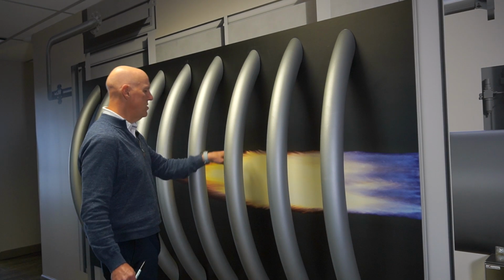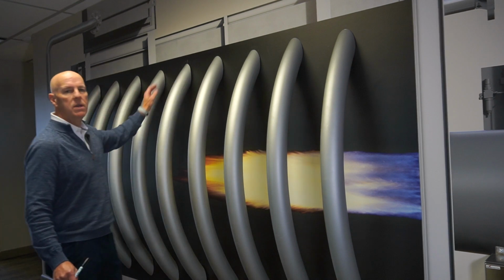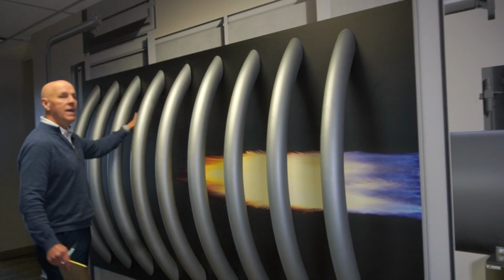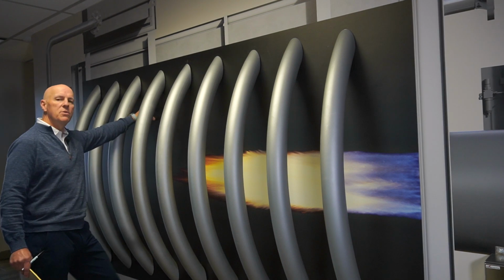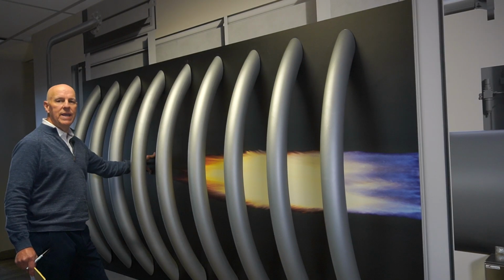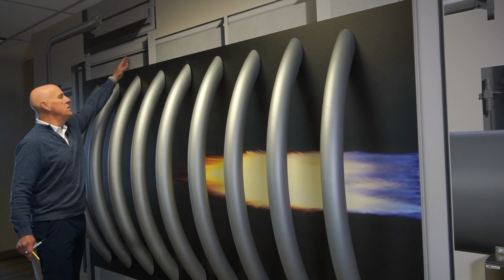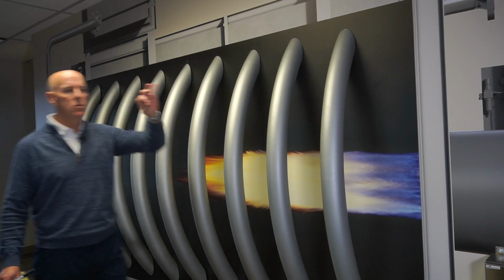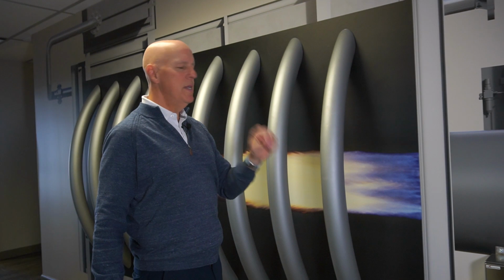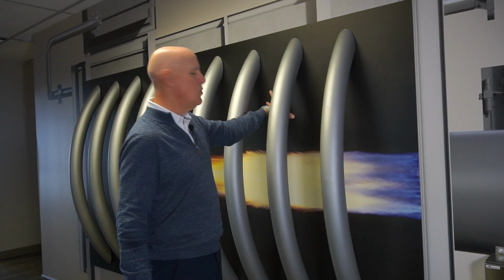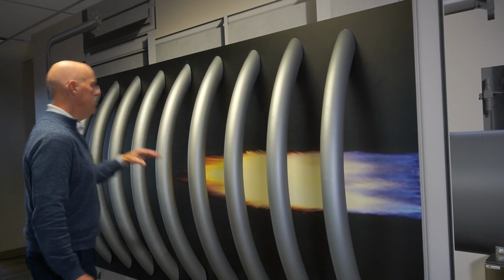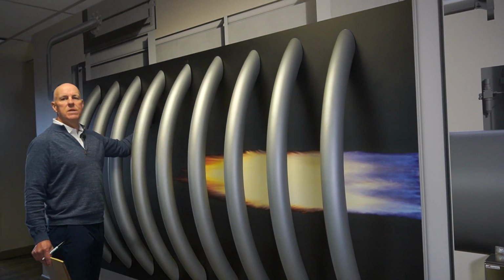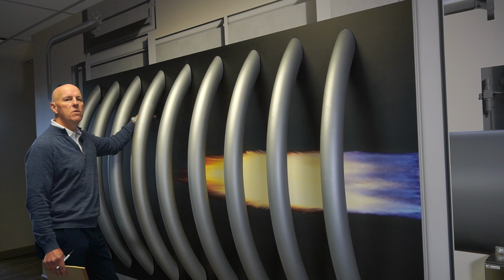Well, this CO continues to burn, it continues to oxidize outside of the flame. There are diffusion type reactions going on where my hand is, and even up into the convection section, because CO will oxidize at about 1200 degrees F. So as long as I'm above 1200 degrees F and there's oxygen present, I can continue to burn the CO.